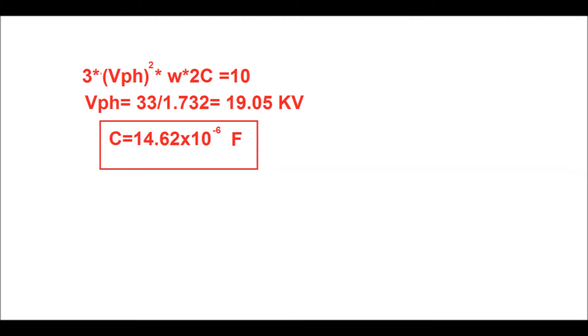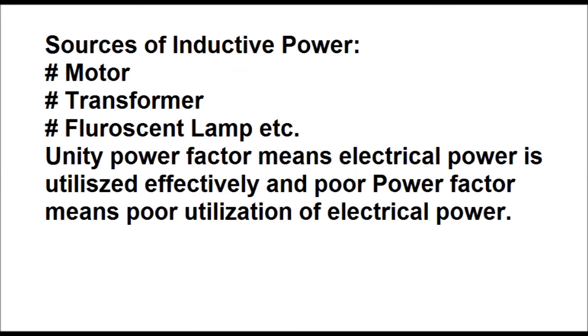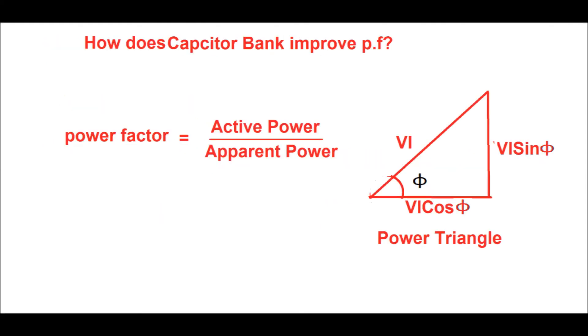What is the use of a capacitor bank in a substation? In a substation there are many sources of inductive or lagging reactive power, such as motors, transformers, and fluorescent lamps. Unity power factor means electrical power is utilized effectively, while a poor power factor means poor utilization of electrical power. The capacitor bank improves the power factor by nullifying the inductive reactive power. The power factor is the ratio of active power to apparent power, as shown in the power triangle: VI·cosφ is active power, VI·sinφ is reactive power, and VI is apparent power.